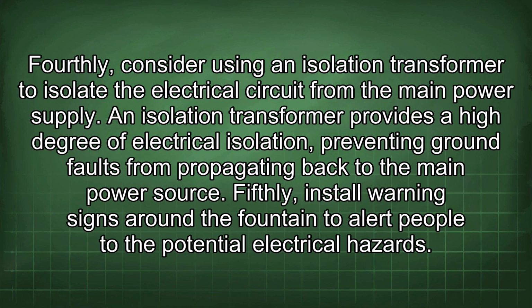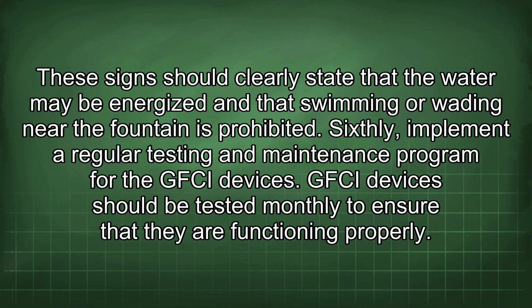Fourthly, consider using an isolation transformer to isolate the electrical circuit from the main power supply. An isolation transformer provides a high degree of electrical isolation, preventing ground faults from propagating back to the main power source. Fifthly, install warning signs around the fountain to alert people to the potential electrical hazards. These signs should clearly state that the water may be energized and that swimming or wading near the fountain is prohibited.